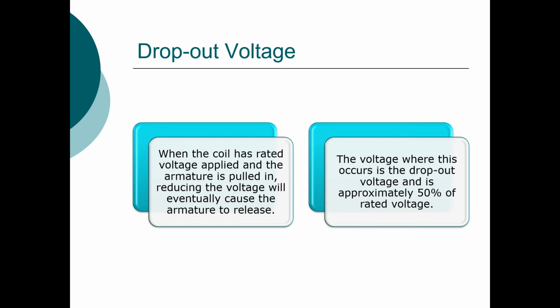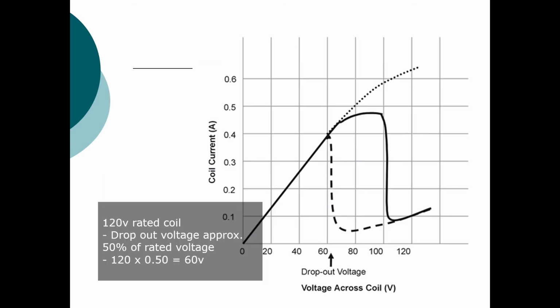The other voltage point we need to be aware of is called dropout voltage, and that's how low the voltage can go before the armature releases and the armature springs overcome the magnetic force. When the coil has rated voltage applied and the armature is pulled in, when we reduce the voltage, we slowly reduce that magnetic field as well. By studying the same graph and looking at the dotted line instead of the solid line, we can see that as we reduce our voltage, at about 50% of our rated voltage, the armature is going to release, and now the springs are going to overcome the magnetic force.